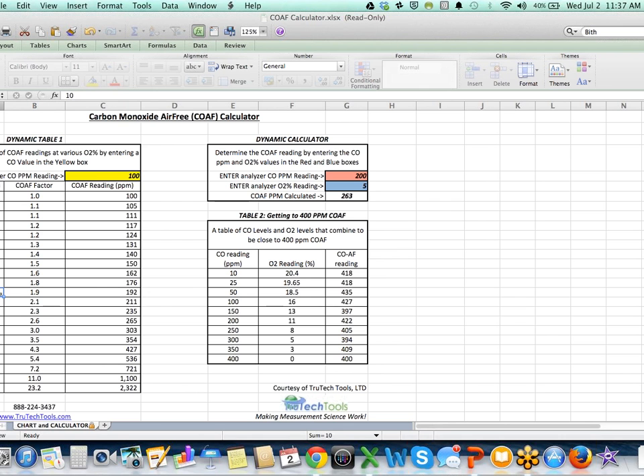Okay. At 10% oxygen, the CO air-free factor is 1.9, or it'd be about 192 will be your CO air-free reading. And so we're typically talking in oxygen levels that are in this range of 5 to 15% oxygen. So you can see there's quite a large multiplier that can get into the 1.5 to 2 to 3 to 4 to multiply your CO reading.